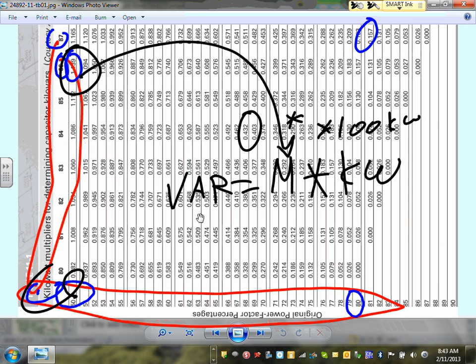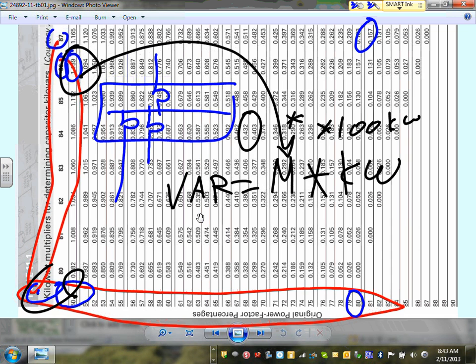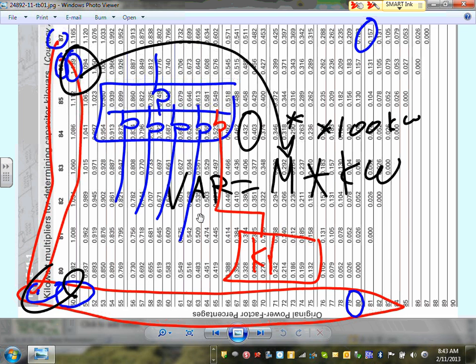That's correcting at the switchgear level. What's correcting at the switchgear level, Jeff? Here's my switchgear that you guys sized with your friend Chad here. So here are multiple loads going on, and I want to correct right here. So guess what they do? They take an overcurrent device and put a big cap, kVAR, and they put a cap. Can you guys see that? They put the cap right at the switch here. Here's my 4,000 amp switch that we're designing for. They put the cap right there.